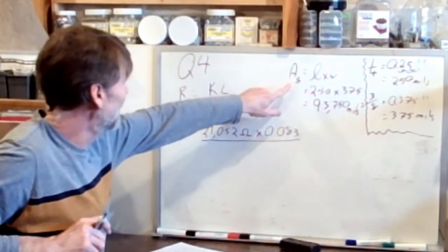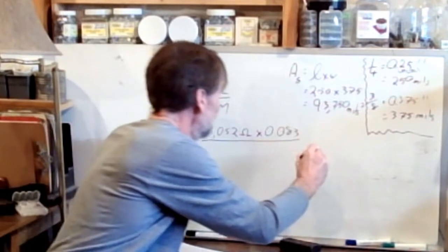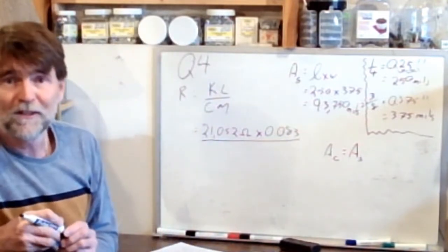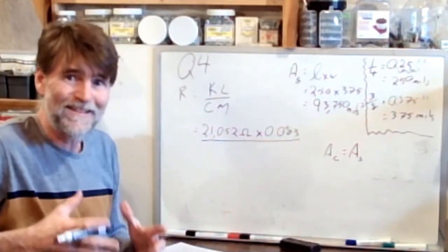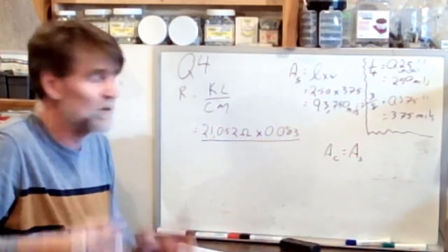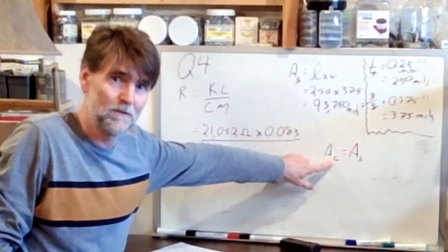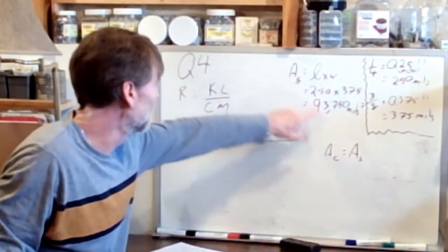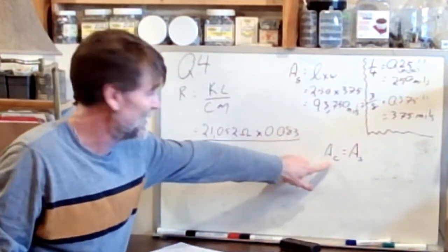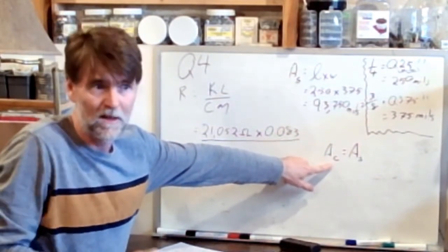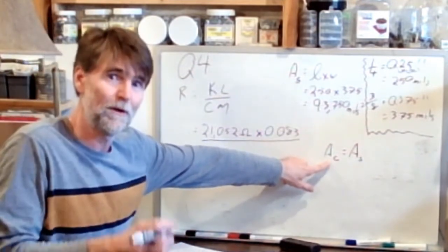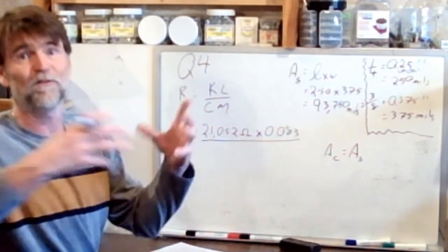So how do we translate from square mils to circular mils? The conversion number is 0.7854. We have to decide whether we're going to multiply by it or divide by it. So remember, one circular area is a smaller cross-sectional area than one square area. This is a smaller unit of measurement, like 1 centimeter compared to 1 inch. A smaller unit of measurement means that to measure the same thing, it's going to have to be a bigger number.